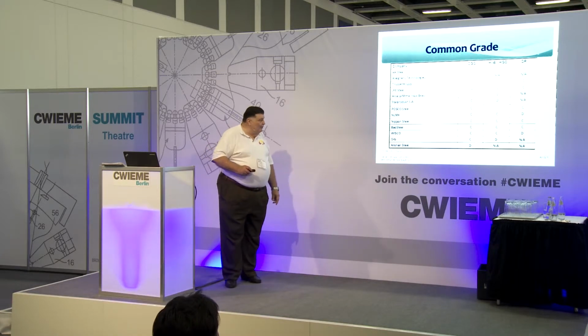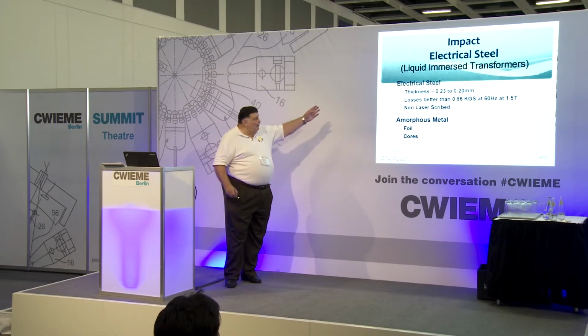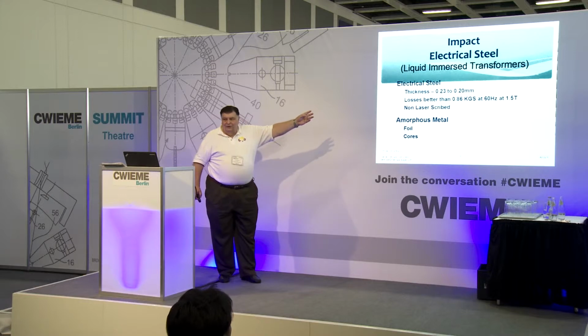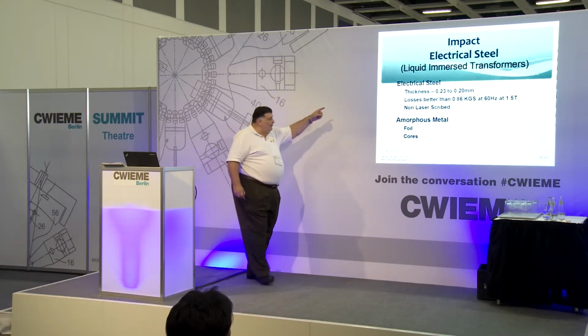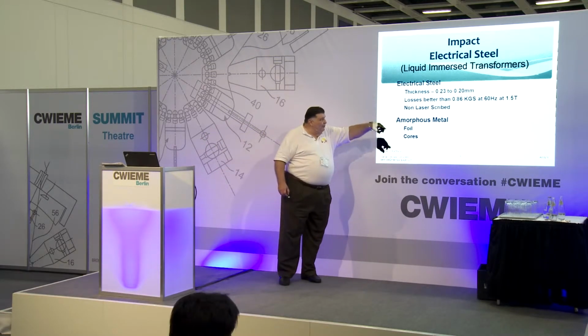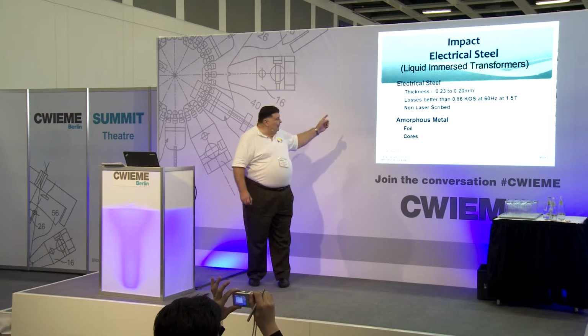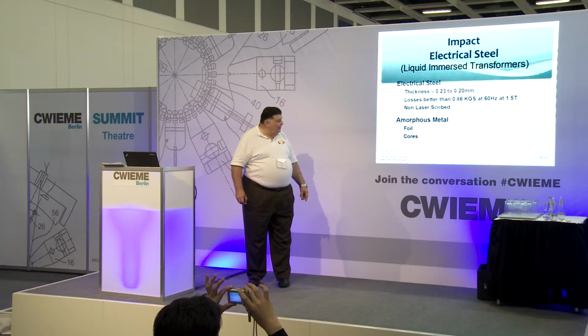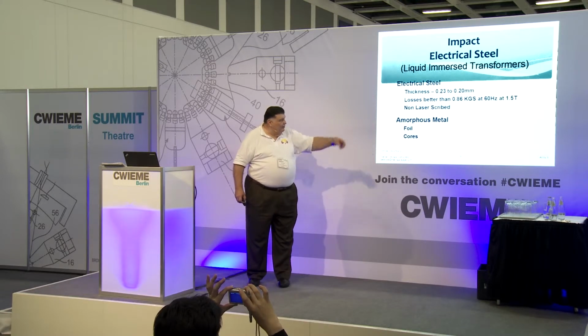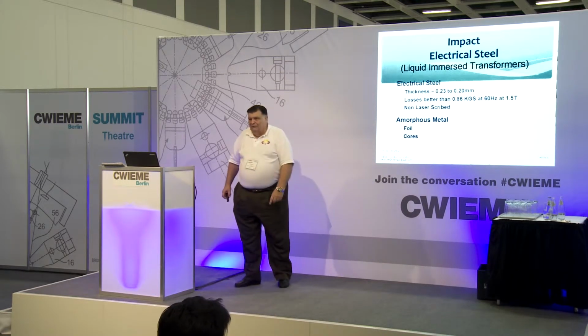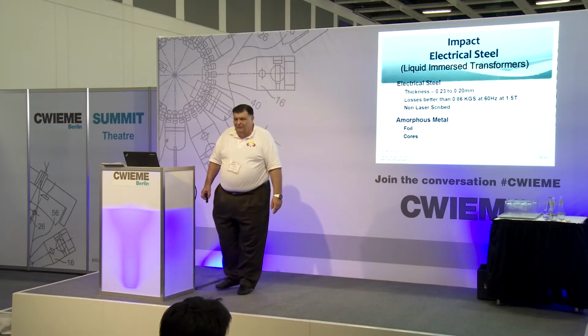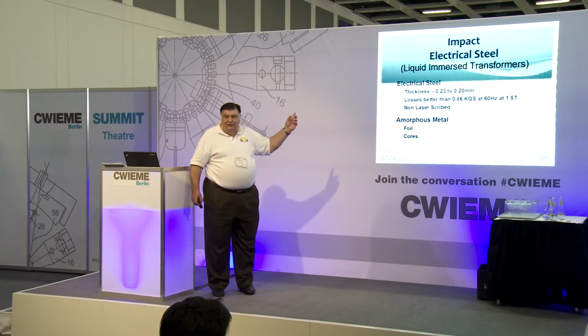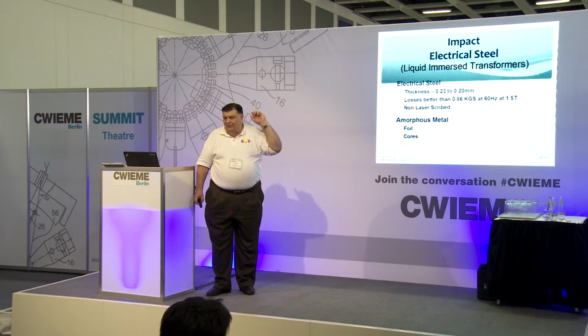So what does that do? Electrical steel, what are they going to be looking for? We're going to be looking for thicknesses in the 0.23 to 0.20 millimeter. Losses better than 0.86 watts per kilogram at 60 hertz, 1.5 Tesla. Non-laser scribe for the US because we anneal the core.